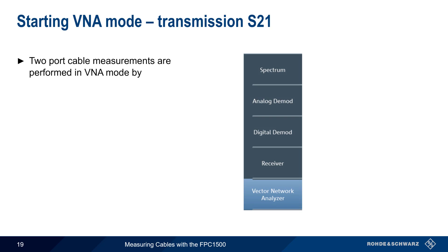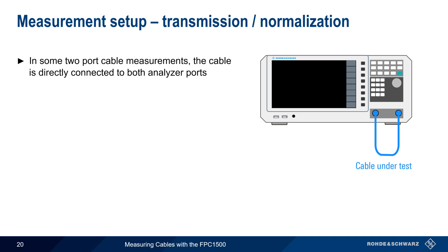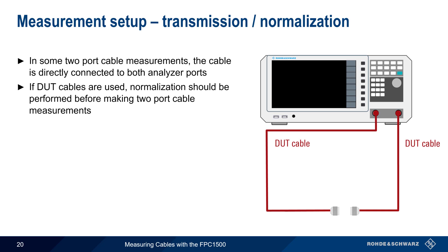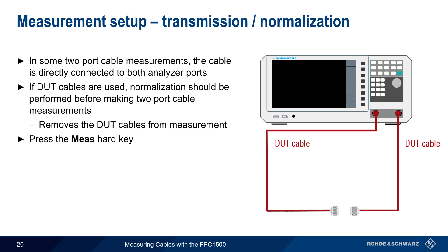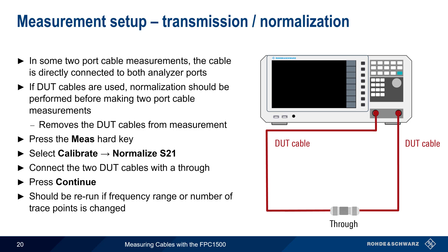To make two-port cable measurements in VNA mode, press the Measure hard key and then select Transmission S21. In some two-port cable measurements, the cable under test is simply directly connected to both analyzer ports. If DUT cables are used to connect the cable under test to the analyzer, then a normalization should be performed to remove the influence of the DUT cables on the measurement. Normalization is run by pressing the Measure hard key and selecting Calibrate, Normalize S21. After a through is used to connect the DUT cables, press Continue to run the normalization. Note that normalization should be rerun if the frequency range or number of trace points has been changed.